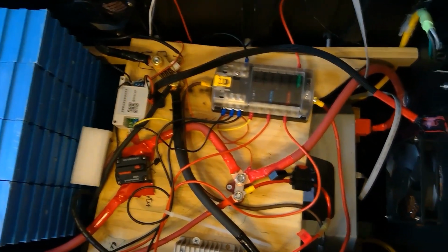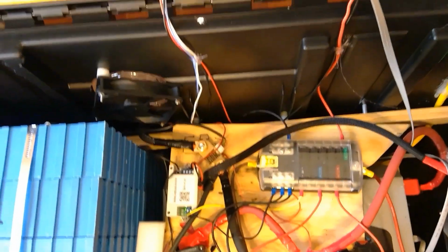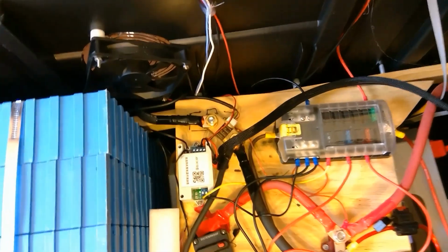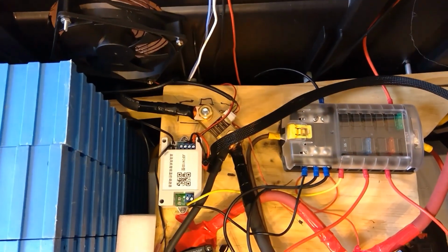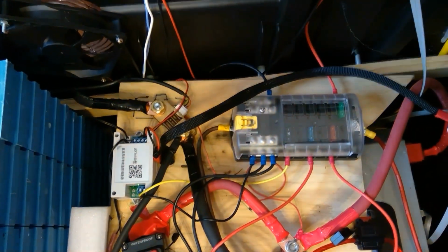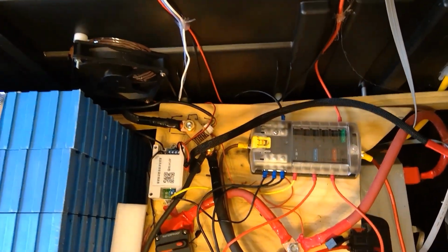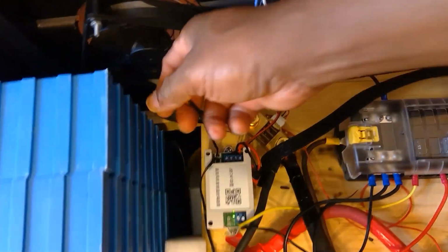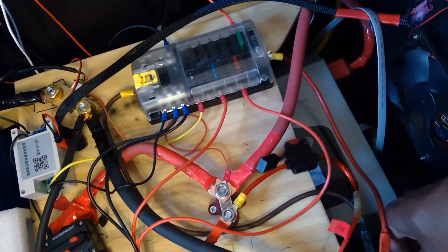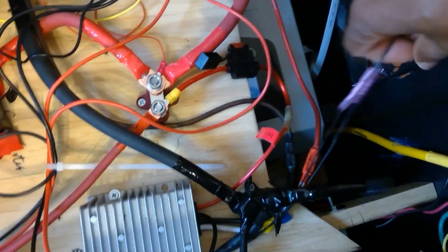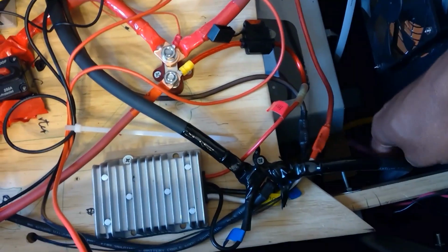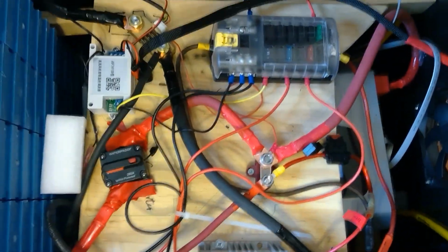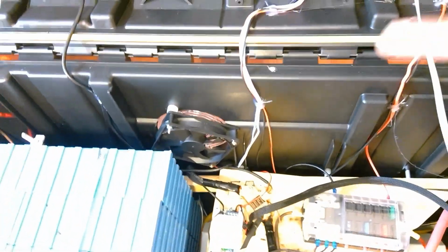Anytime this system gets hot, these intelligent fans operate only when the temperature increases, so I set the temperature to trigger the fans. Fan one has its probe on the side of the battery, and the other fan has its probe close to the inverter. If that side gets hot, the corresponding fan will turn on.